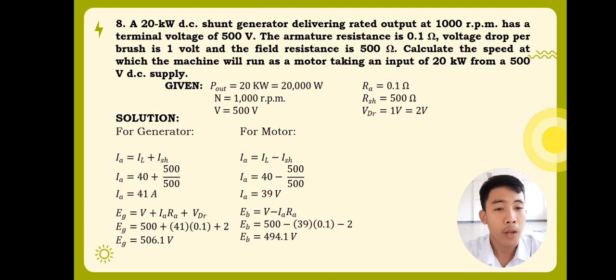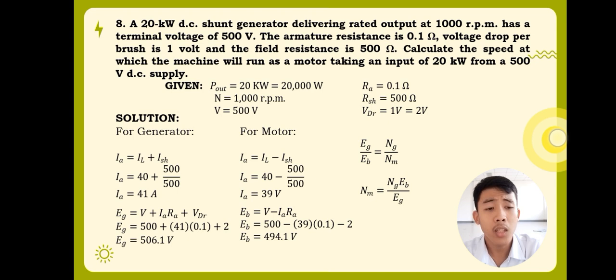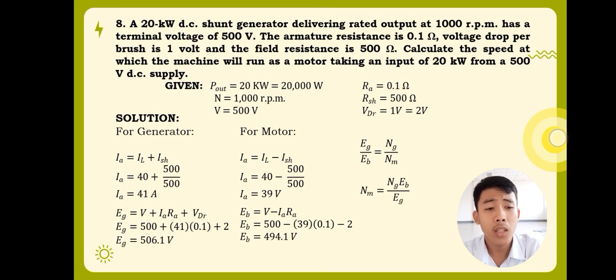Lastly, to calculate the speed at which the machine will run as a motor, taking an input of 20 kilowatts from a 500 volts DC supply, we will now use the formula, EG over EB is equal to NG over NM. The NG is for the speed of the generator, while the NM is for the speed of the motor. And since we're finding the speed of the motor, we would isolate NM, which would yield NM is equal to NG times EB over EG. So that means the speed of the generator times the back EMF divided by the generated EMF. Substituting the values, now we will have the speed for the motor is equal to 1,000 times 494.1 all over 506.1. And when input in a calculator, calculated, the value for the speed of the motor is equal to 976.28 or 976.3 revolutions per minute.